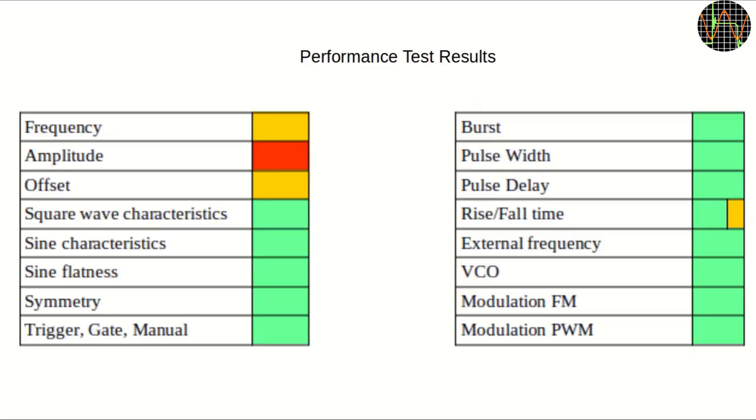At the end of the performance test, this is the scorecard. Frequency is generally OK except for below 1Hz which needs to be adjusted. Amplitude for all three waveforms is out of spec and has to be adjusted and I might want to try to adjust the offset slightly. On the lead trail test there was one value where the trail was slightly above the tolerance but that is not something easy to fix so I decided to live with that. Everything else is still within tolerance after so many years and serious falls. An amazing result.